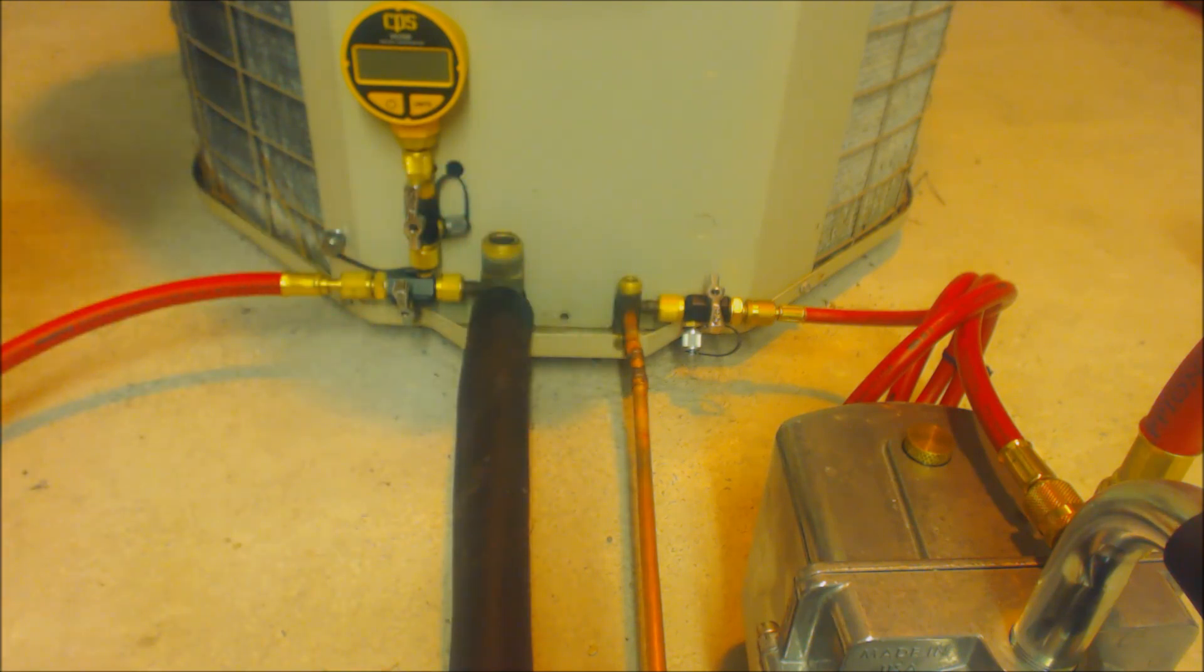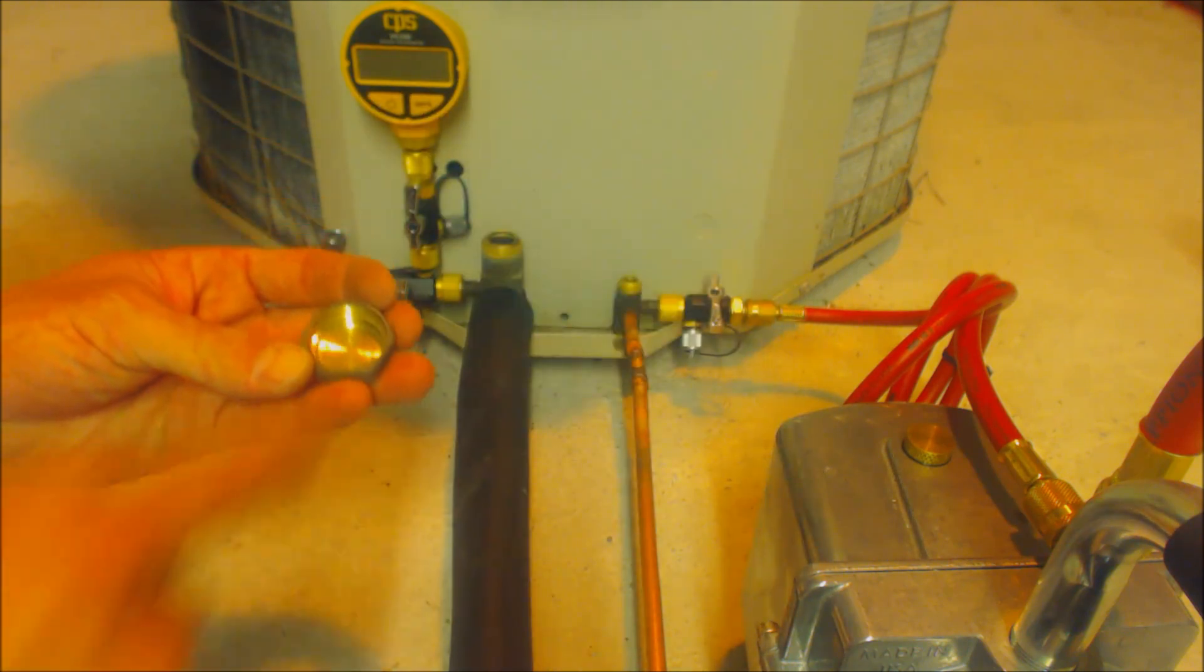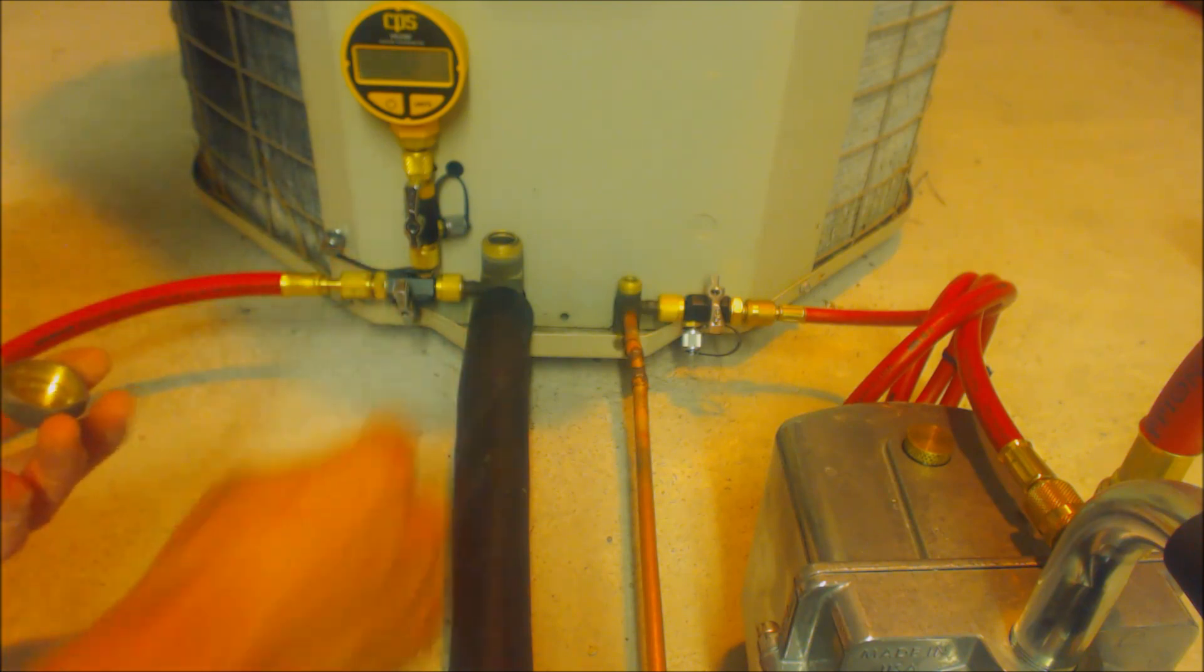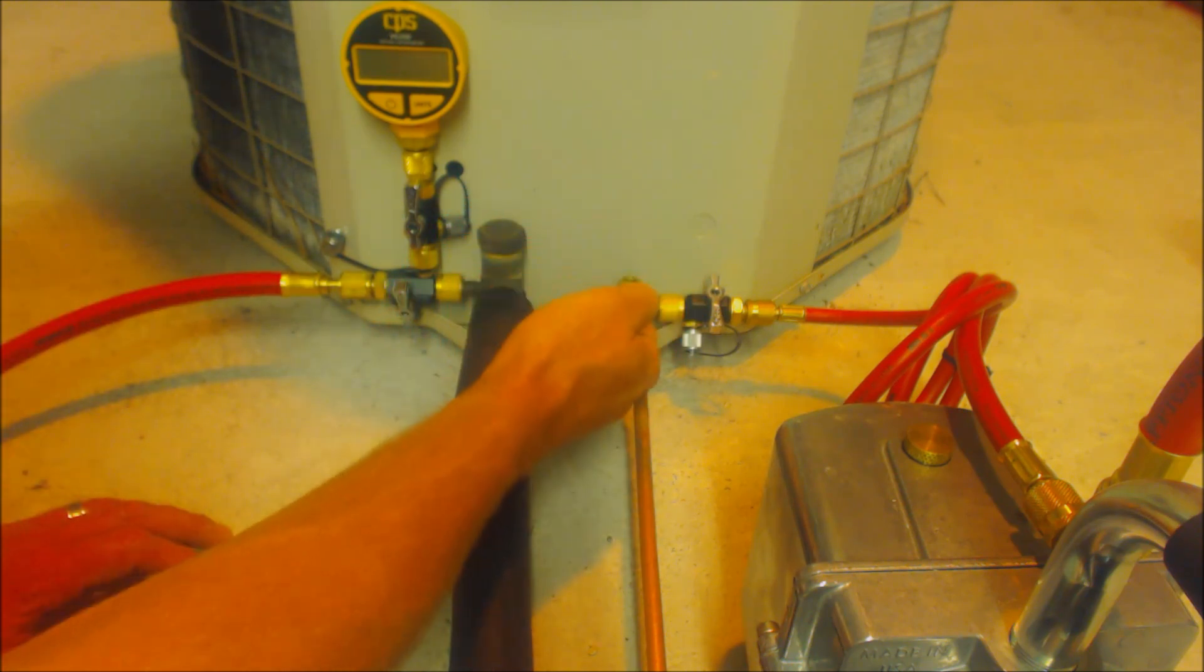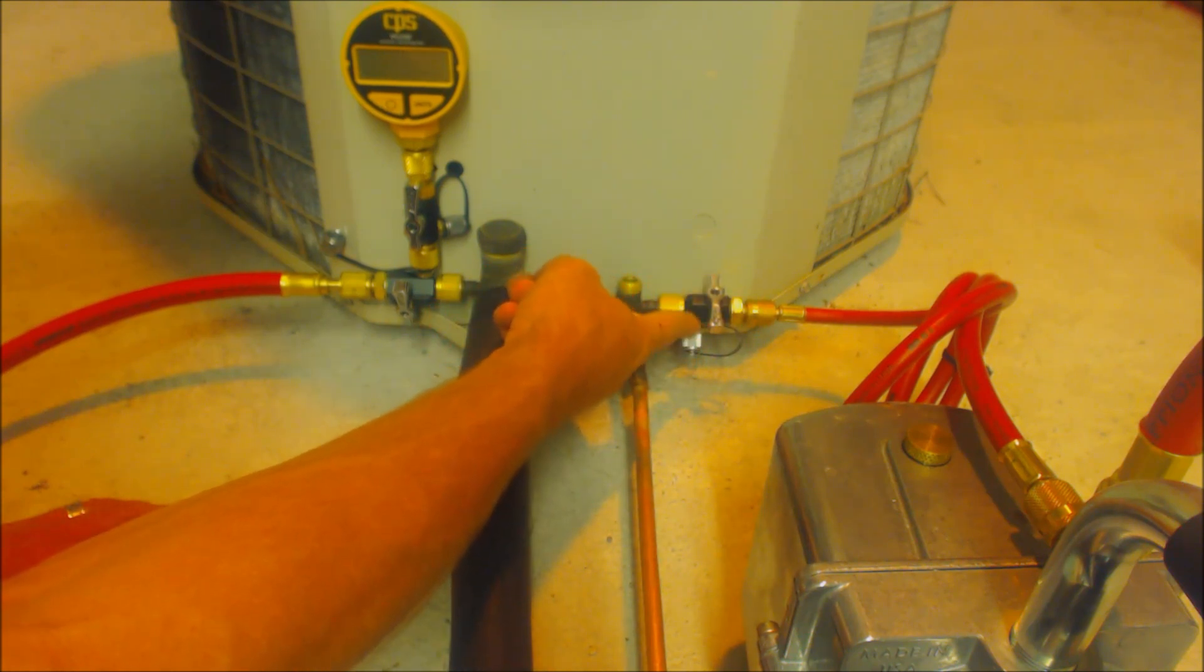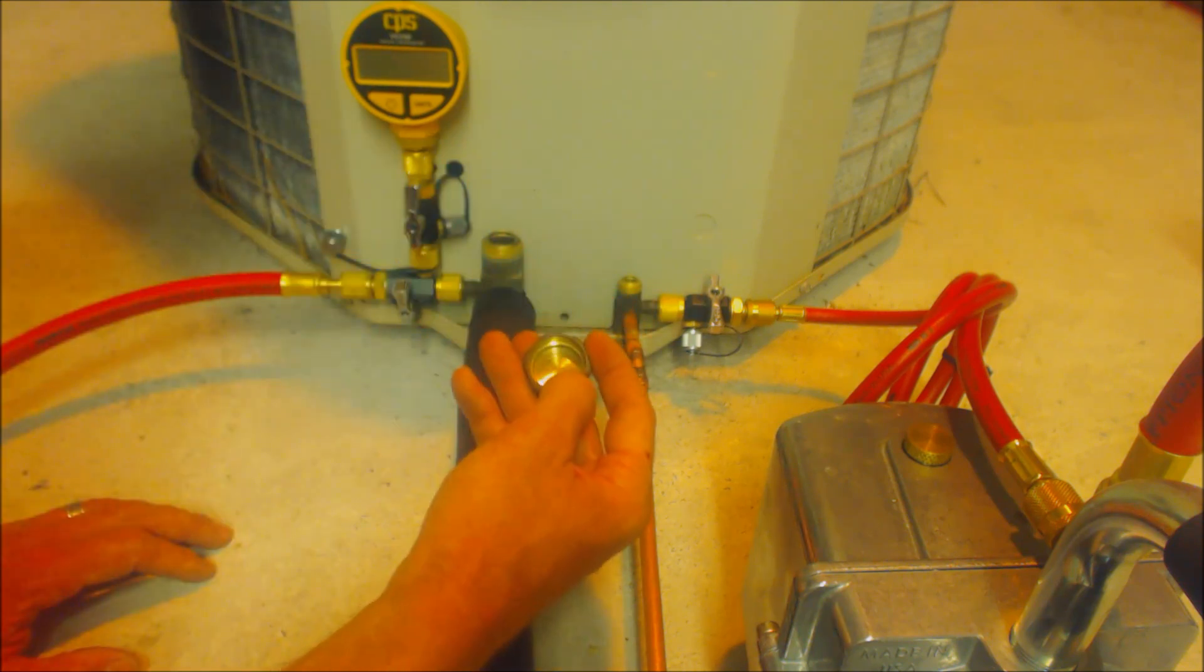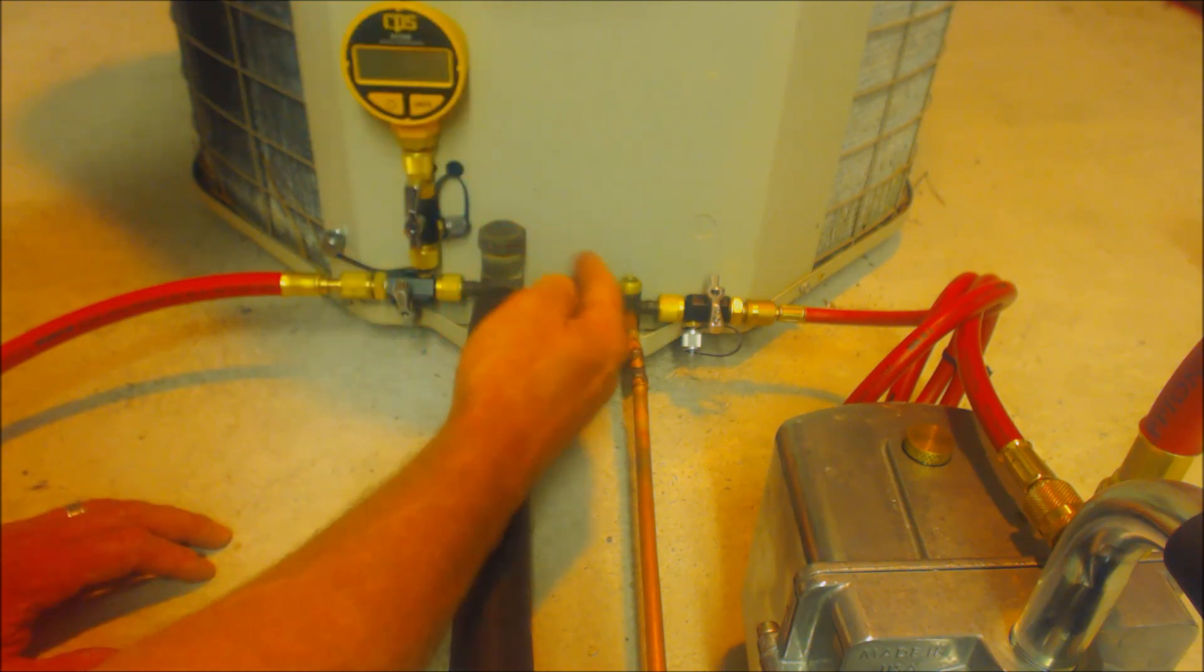But sometimes that works. Another thing that you can do is you take your valve cap right here and you put a little dab of refrigerant oil on the inside of the valve cap and you rub it on just like this and put a little bit more refrigerant oil right around here. You put your valve cap on so you got to figure which one is the one that's leaking and you want to put the valve cap on the one that's leaking and the other one is how you're going to either break the vacuum with refrigerant from the system into the lines or if that manufacturer says that they don't want you to open the valve, say if it's the liquid line, you can break the vacuum with liquid refrigerant right into the liquid line. Sometimes it's recommended just to put a little bit of refrigerant oil on the cap and on here and seal this down after you're done installing the system.